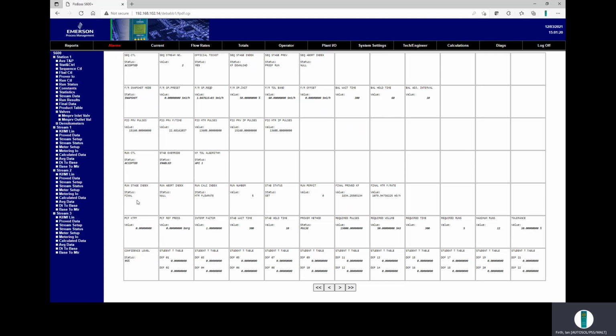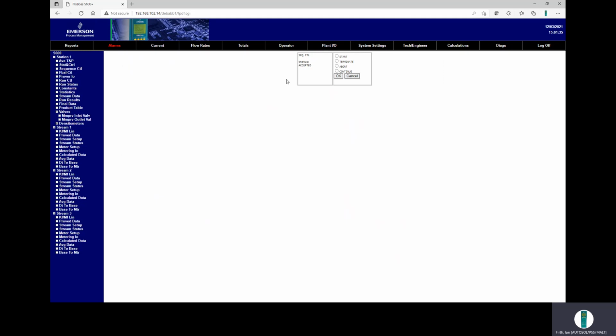Now we're down to final. K factor download, and now we're awaiting a reprove. If you did want to do a reprove, say an hour or a certain period afterwards, you would just literally go to there and press continue, and it would then do a reprove with exactly the same settings that you've just used.